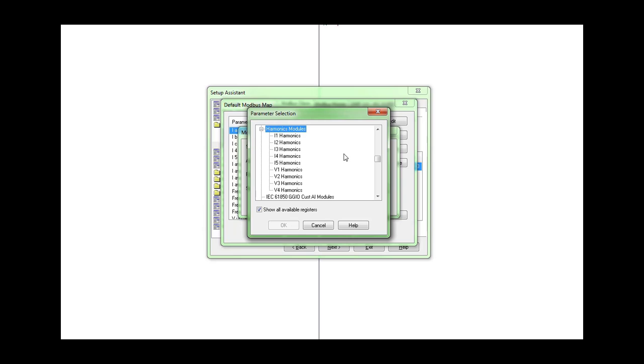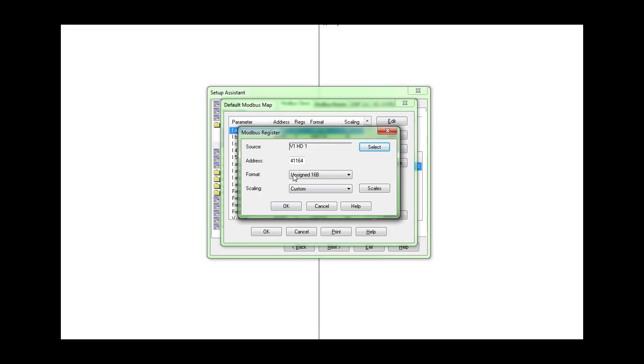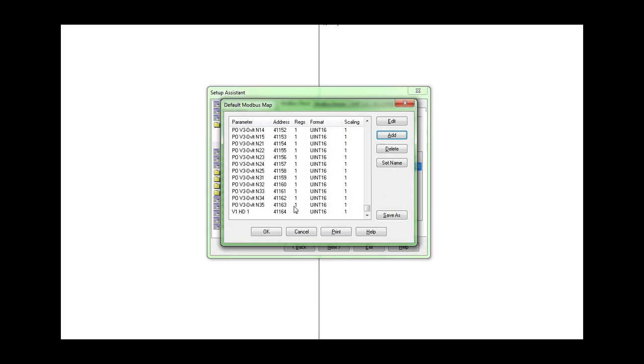What I'm going to do is select the voltage harmonics of phase number 1, and now you can see the 63 different harmonic values for the voltage of phase number 1. I will just pick the first harmonic value of voltage phase 1. That means voltage 1, harmonic value number 1. That assigns us a Modbus address, 41164, and we can leave the other parameters at their defaults.